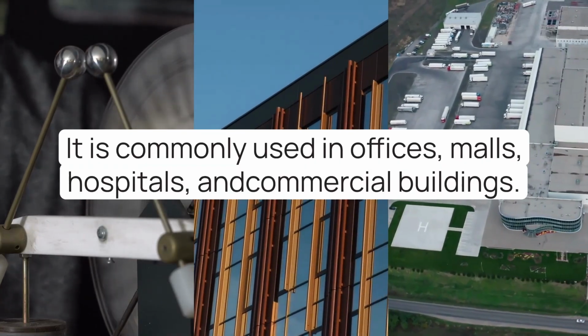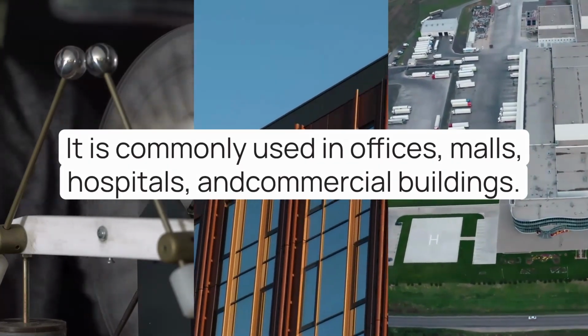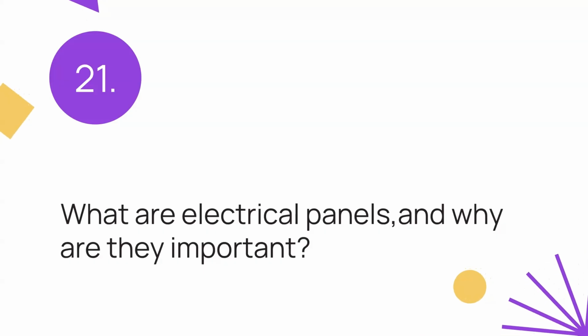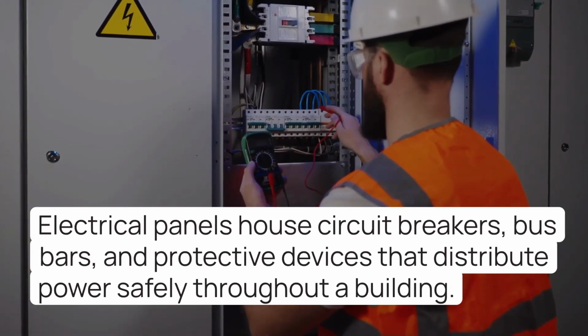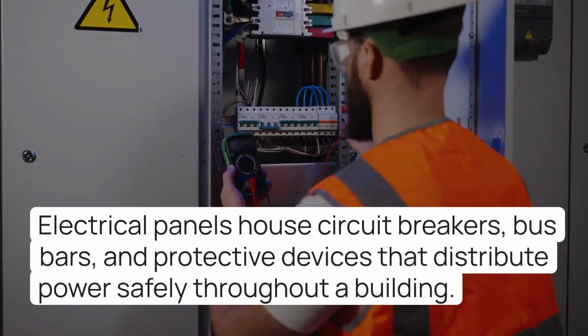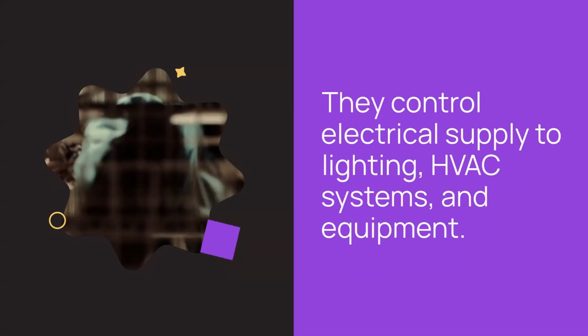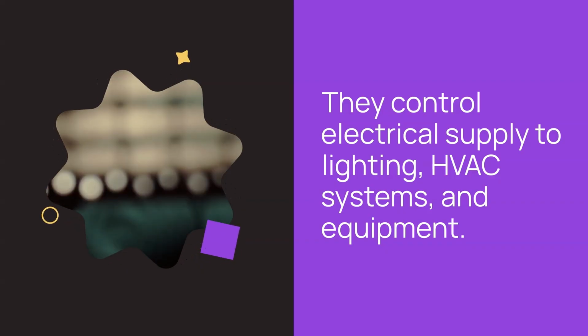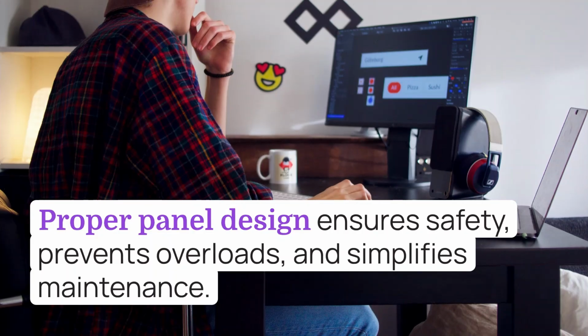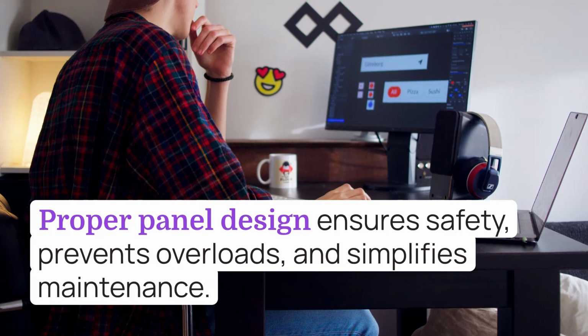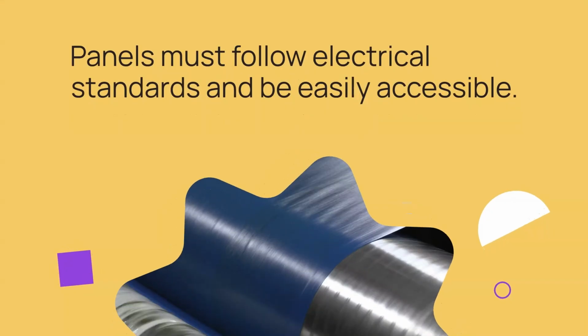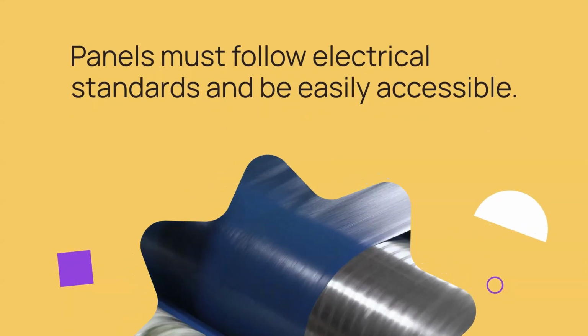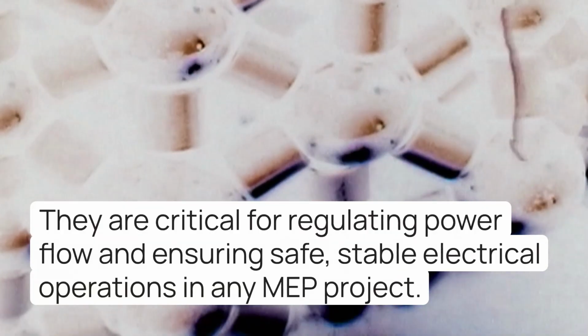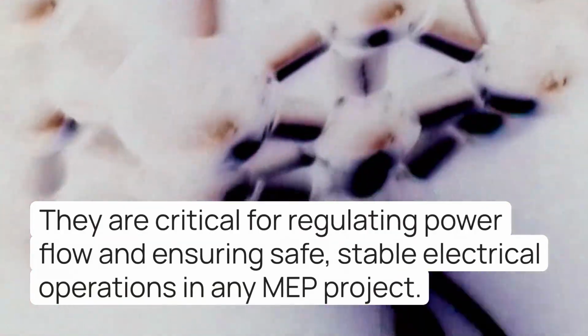It is commonly used in offices, malls, hospitals, and commercial buildings. 21. What are electrical panels and why are they important? Electrical panels house circuit breakers, bus bars, and protective devices that distribute power safely throughout a building. They control electrical supply to lighting, HVAC systems, and equipment. Proper panel design ensures safety, prevents overloads, and simplifies maintenance. Panels must follow electrical standards and be easily accessible. They are critical for regulating power flow and ensuring safe, stable electrical operations in any MEP project.